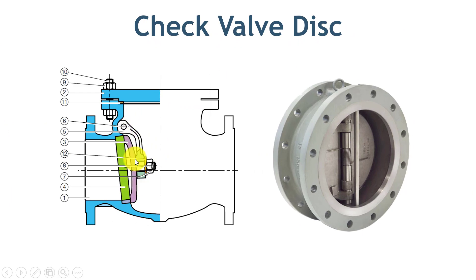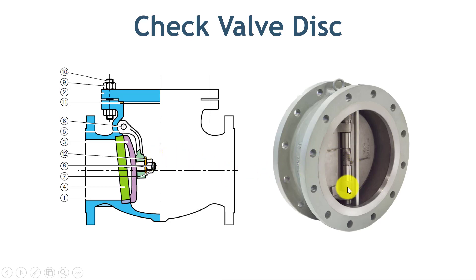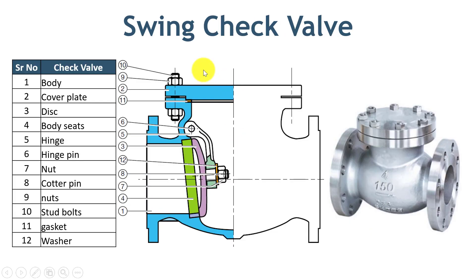The disc in swing type and tilting disc check valves is connected with a hinge and hinge pin, which allows the disc to move freely with forward flow and close when there is not enough forward pressure. A spring in the folding disc and tilting disc check valve helps the valve react quickly and close in the event of pressure loss. There is no stem in the check valve, so you cannot determine the position of the valve from the outside.